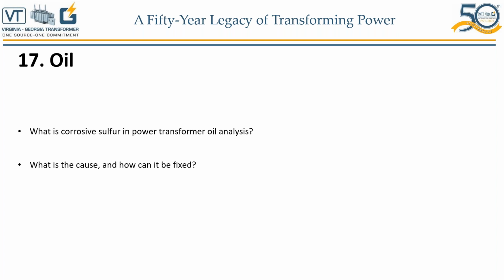Worst case is, imagine your winding conductor paper wrapped, and you have now copper sulfide building up. What this does to insulation, the paper, is it starts degrading the paper because of copper sulfide, because all of a sudden the paper, which is supposed to be just cellulosic material soaked in oil, now it's got copper sulfide in it. So what happens to the dielectric strength of that paper? Obviously it reduces. So in a nutshell, that's what corrosive sulfur is.